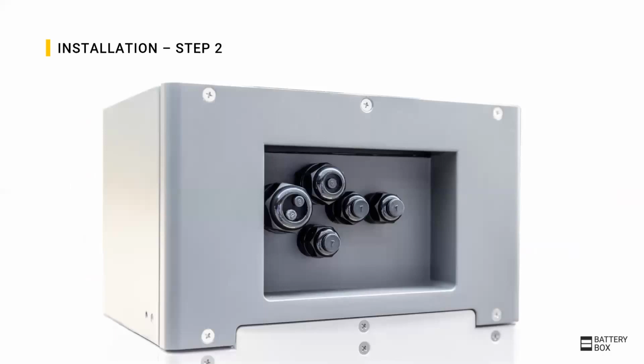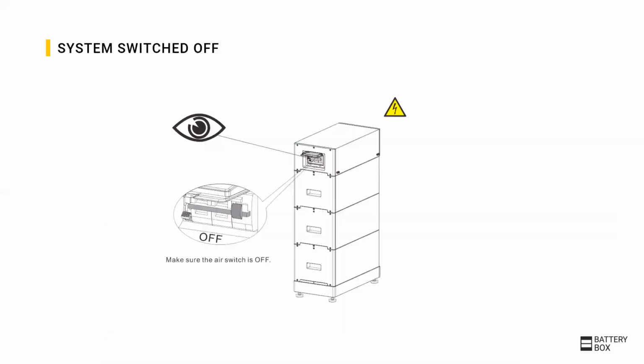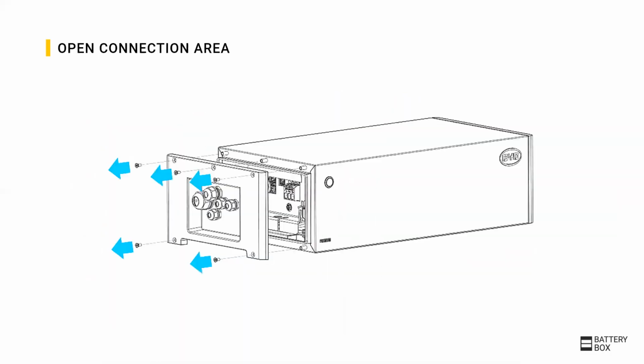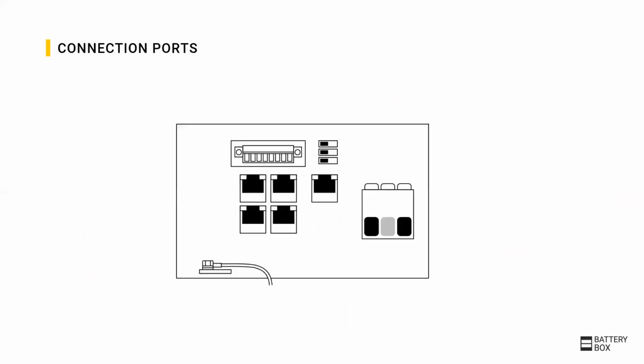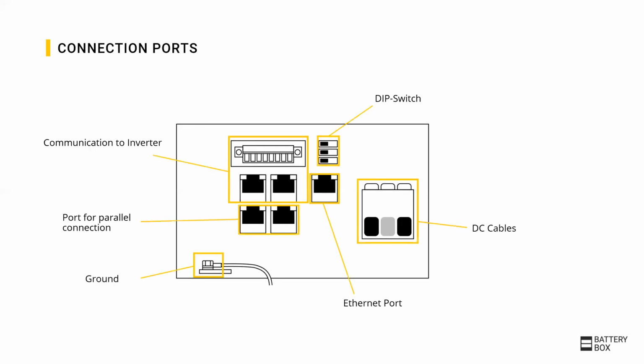The next step will be the external cable connection on the left side of the BCU. Make sure the system switch is off before you start. Then open the connection area. Here you see the ports available in the connection area. You have the communication ports to the inverter, the ports for the parallel connection, the ground, the Ethernet port, the DC cables port, and the dip switches.